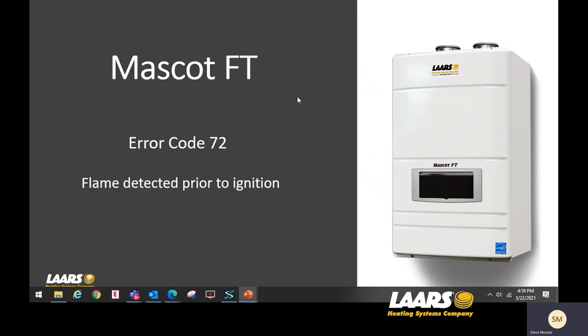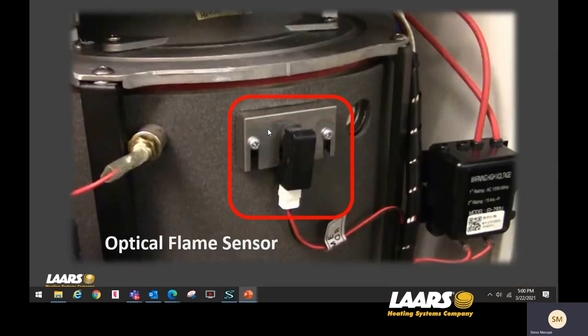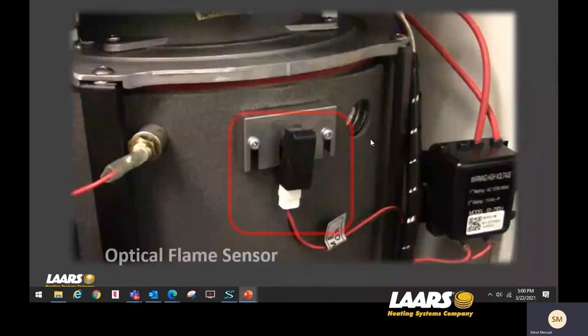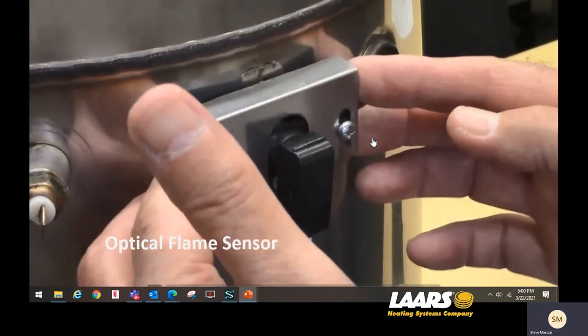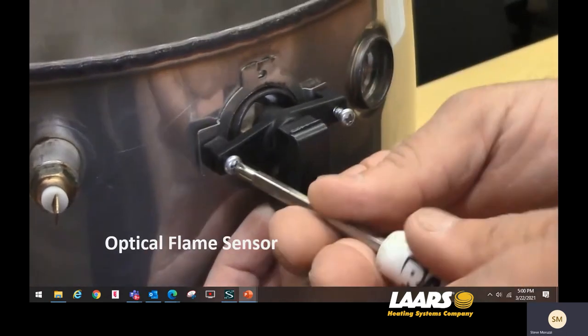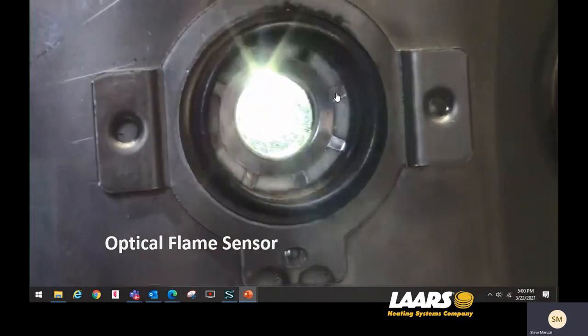Next, error code 72 — flame is detected prior to ignition. On a few examples there has been sawdust or dust on top of the burner. If you run the boiler for a while and the burner plate gets hot, these little pieces of wood or sawdust will start to burn and glow cherry red. The optical eye senses this, and after shutdown when it's still glowing the optical eye sees it. On the next call for heat, it generates the error code. To diagnose, remove the optical eye — we put a flashlight in there to show you how any glowing would be detected. A dirty burner can cause this error code.